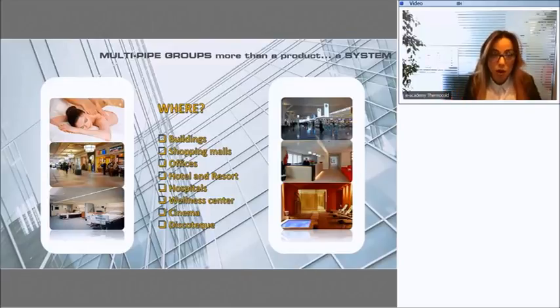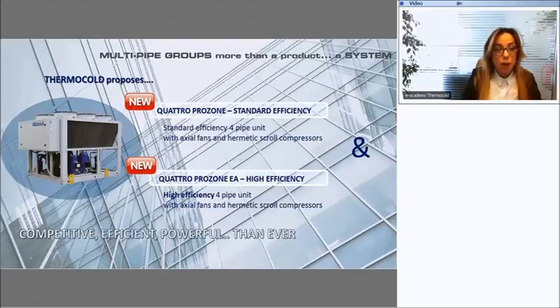Cinemas, due to the highly crowded environment, especially during winter, you may need to produce chilled water for the air conditioning, as well as for discotheques. But another typical example is the office building, which is exposed at one side on the north and the other side on the south. So especially during middle seasons, in this specific application, you may need to produce hot water for the space heating needed in one side of the building, while on the opposite side of the building, you may need to produce chilled water. So, as you can see, a multi-pipe unit has several possible applications.